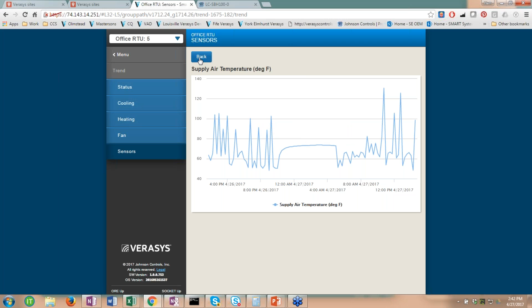Matter of fact, twice today it also went into heating, that's why you've got 130 degrees supply air temperature. Actually, 4 times today it's gone into heating as well. This is a changeover bypass system, and as you know, you go back and forth between heating and cooling to satisfy the zones within the system. That's the beauty of it, I guess, probably beauty isn't the right term.